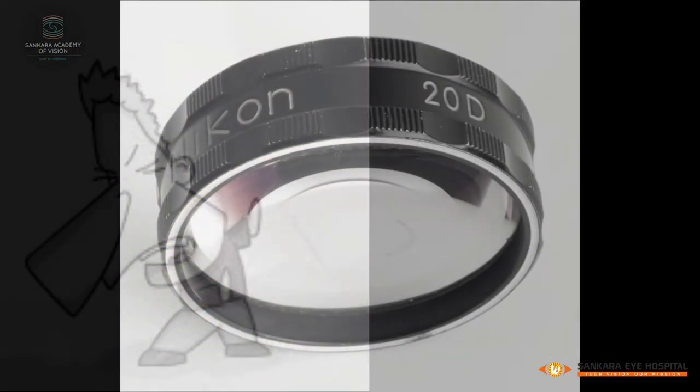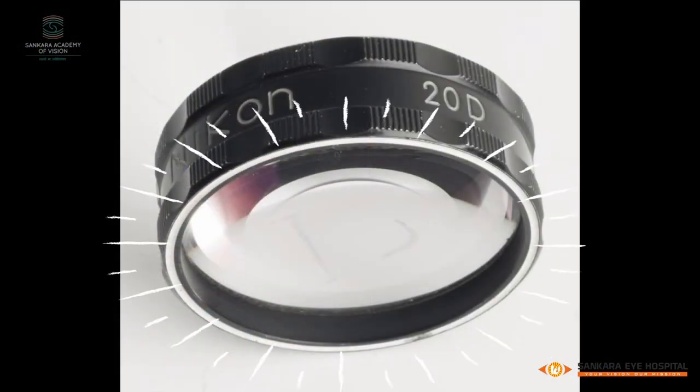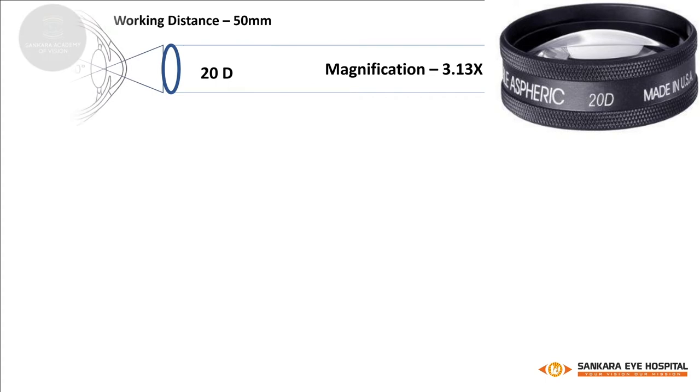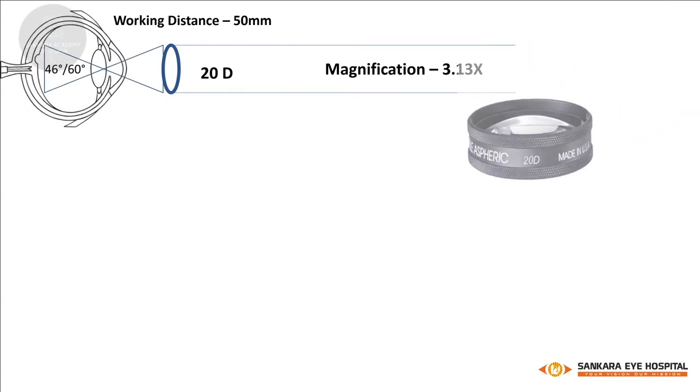Usually the steeper surface, which is indicated by the white markings on the rim, faces the patient. The 20-diopter lens is the most commonly used binocular indirect ophthalmoscopy lens. It has magnification up to 3.13 times and 60 degrees dynamic field of view.